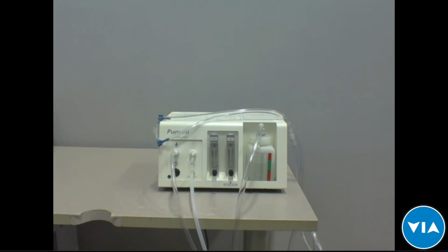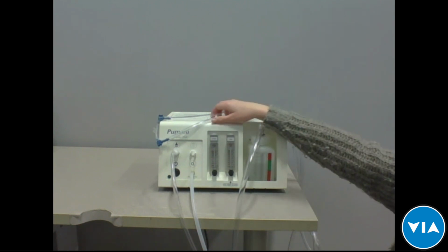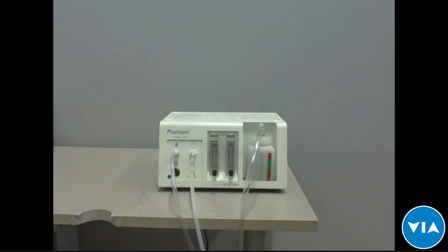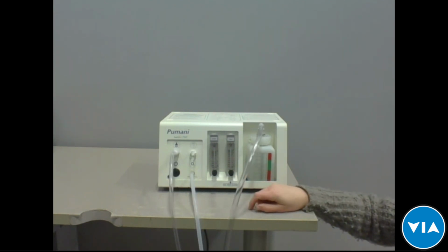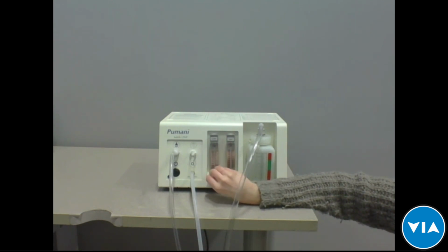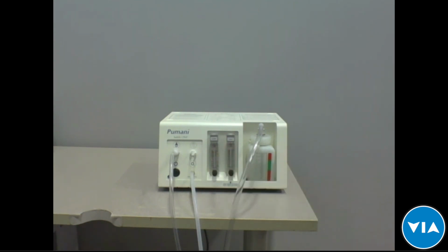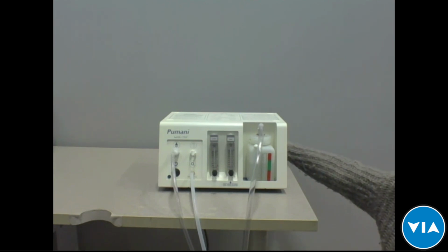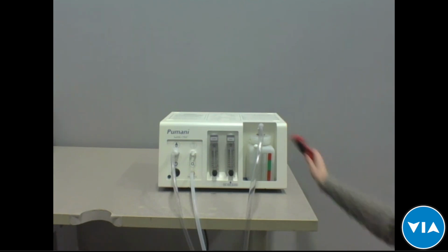the most likely issue is that there's a tube disconnected inside of the machine. This happens if the knob on the oxygen flow meter is not open at some point when the oxygen is connected, which is an easy mistake to make, and there's enough pressure, the tube will pop off on the inside of the machine in order to avoid any damage to the pump in the machine. But it's a very, very easy fix.